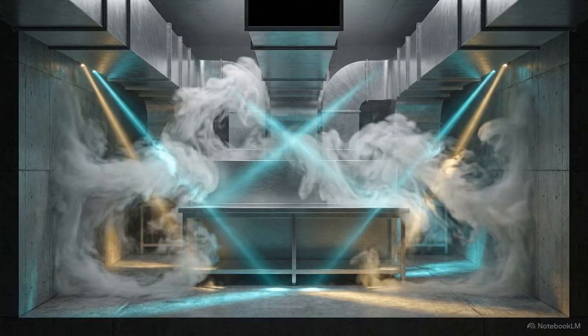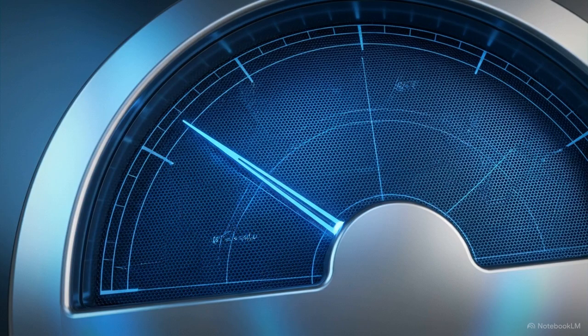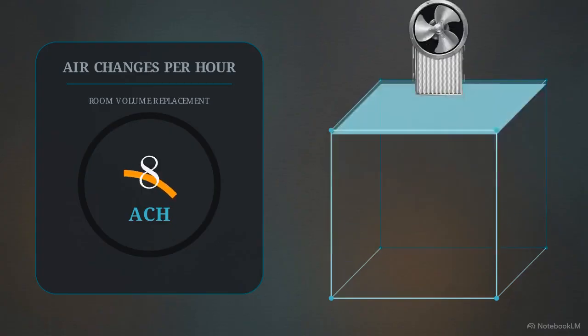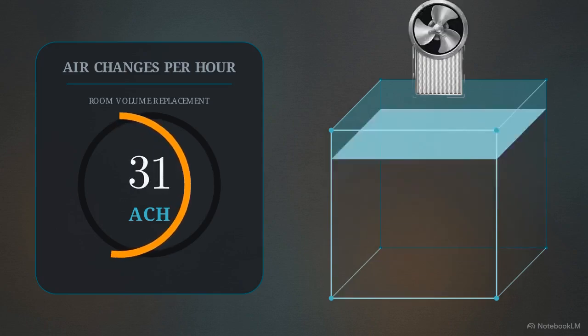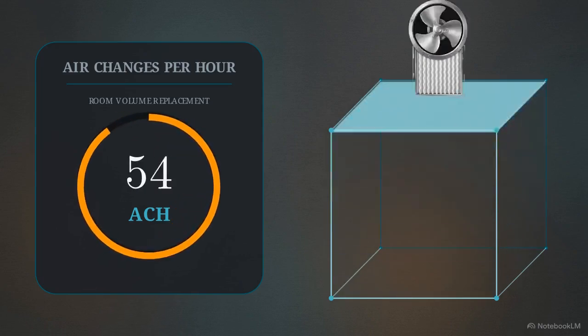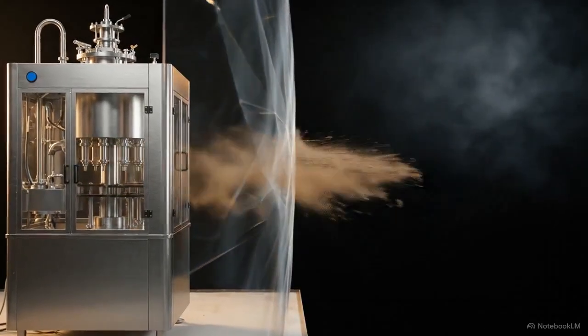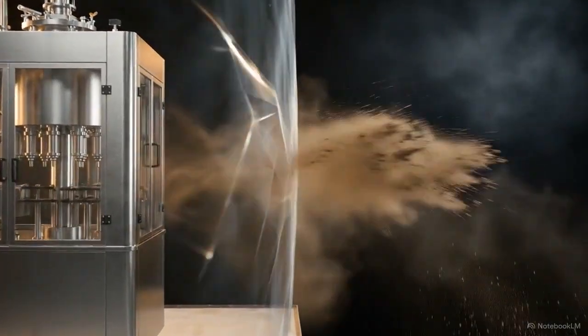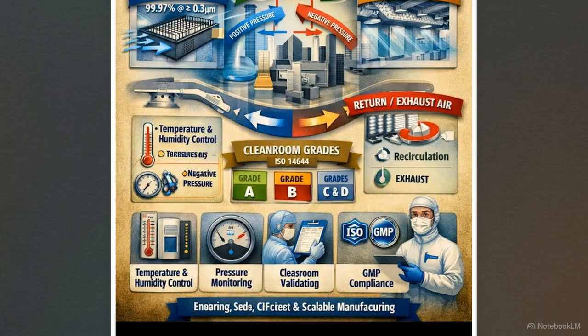This is distinct from turbulent airflow, which is used in less critical zones to mix the air and dilute any stray contaminants. To maintain these dynamics, the system executes a high rate of air changes per hour, or ACH. A clean room typically undergoes 20 to 60 complete volume flushes every single hour. By controlling airflow geometry and pressure cascades, the HVAC system creates physical walls out of thin air, forming a defense against cross-contamination. This engineering maps directly to the ISO 14644 standard.